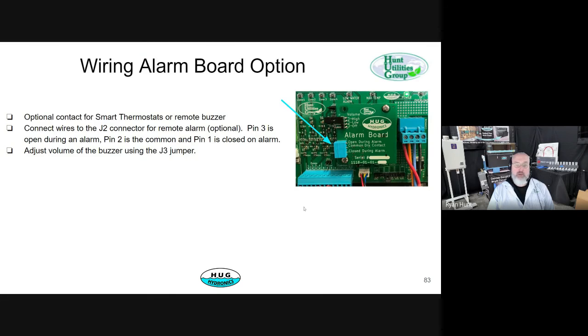The alarm board option is, the alarm board is not optional anymore. It's on every unit. We just put it on there. It lets you set the volume of an alarm. The alarm goes off when the water level gets low or when a fuse blows, but we've never had a fuse blow ever in the field.